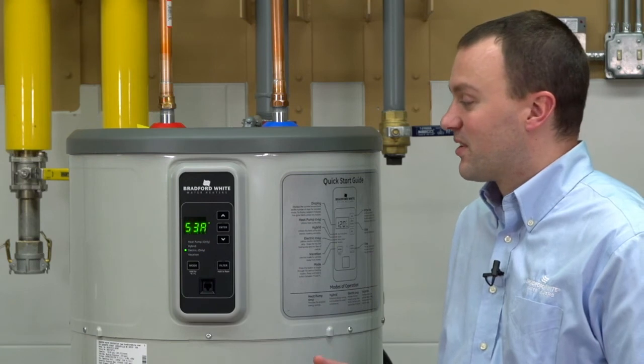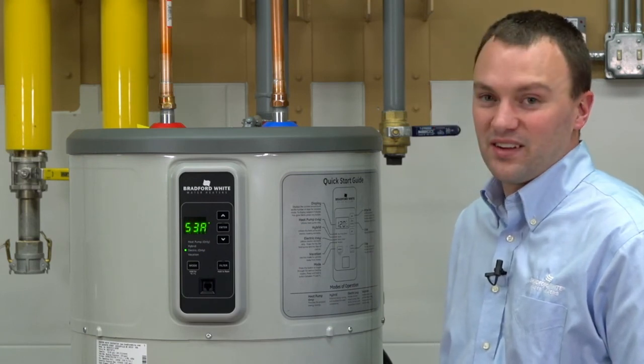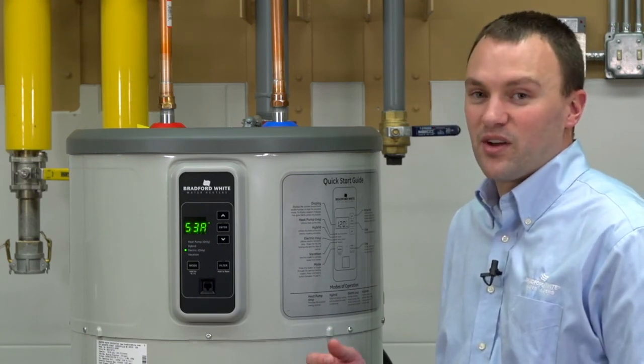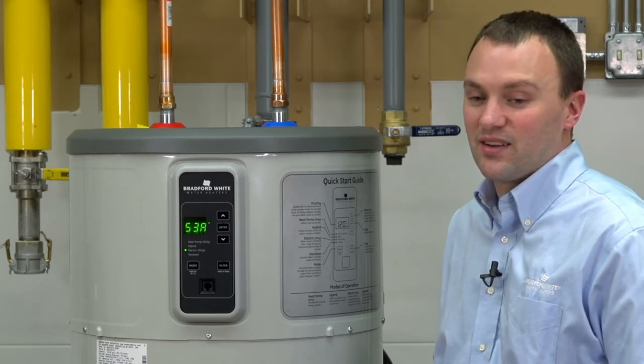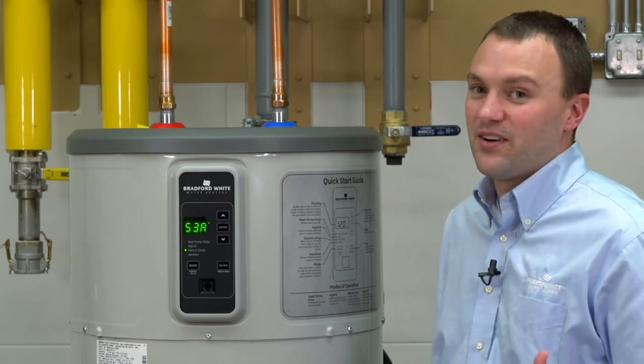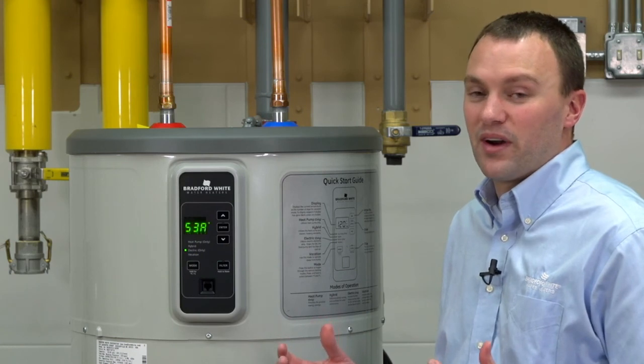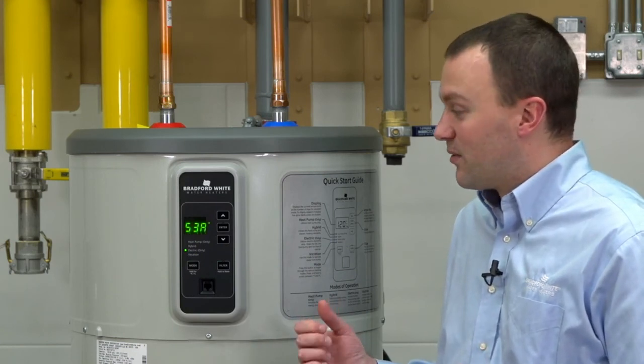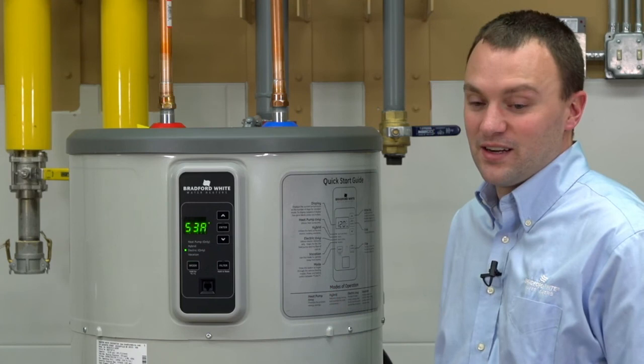Again, the only time we're typically going to run into this is if we're replacing a control, but we can always go in and verify the settings. This is important because both the 50-gallon and the 80-gallon have their own parameters, so making sure we have the right personality set to the right heater.